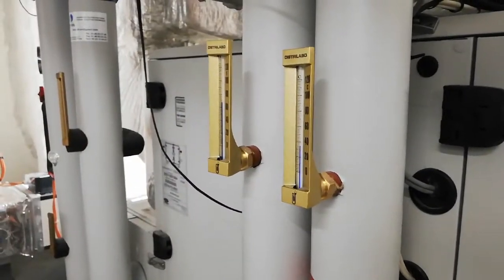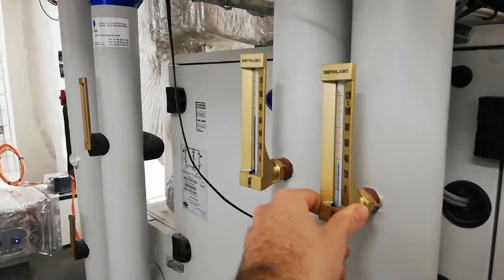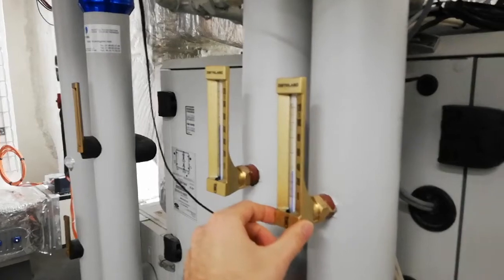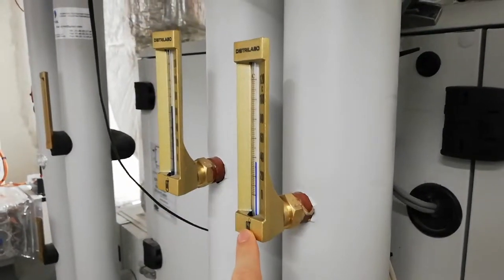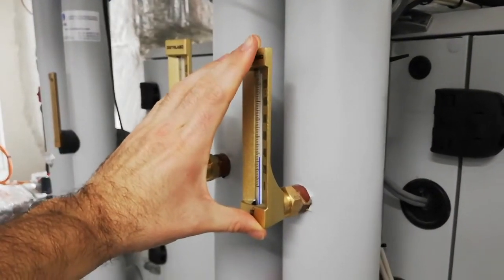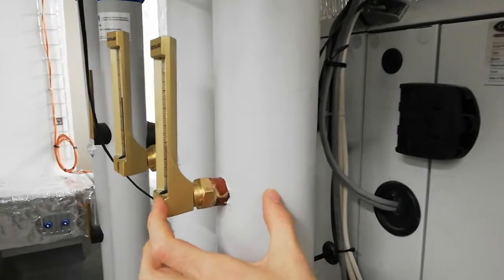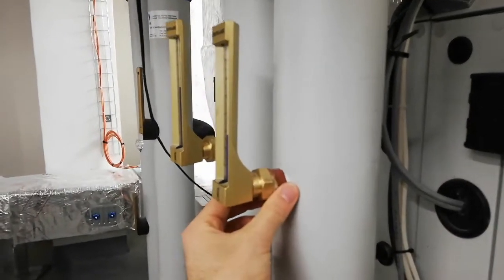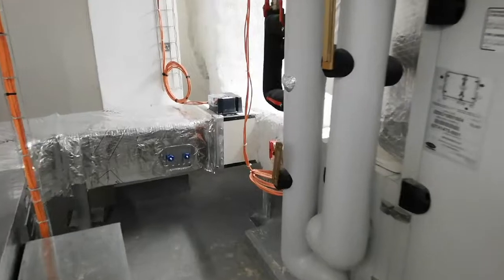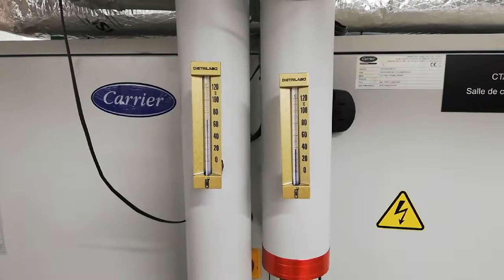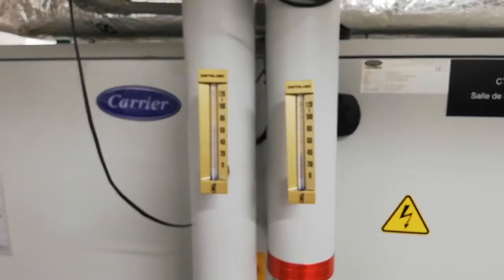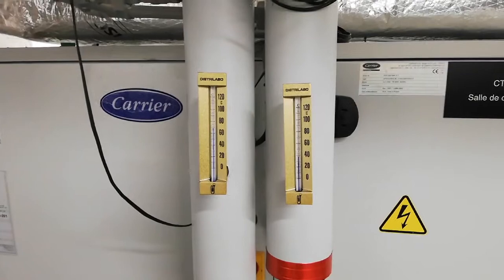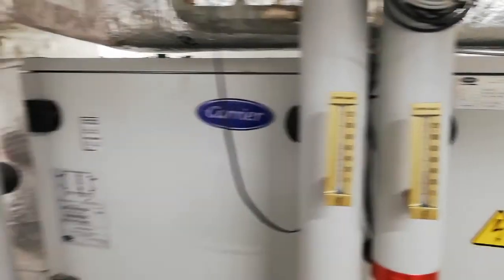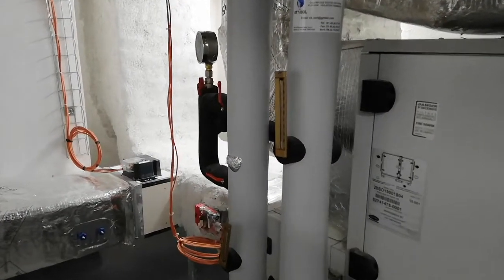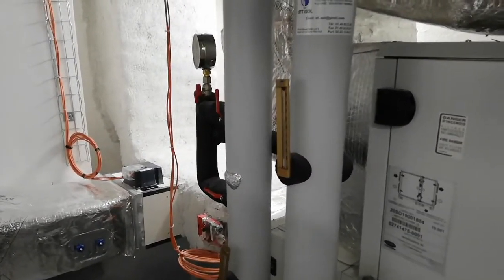Then don't forget to install industrial thermometers. These are 90 degree angle industrial thermometers, because you have this 90 degree angle here. This one has a 150 millimeter case and a 63 millimeter stem, which is the length of the small part going inside the flow to measure the temperature. We have the same on the chilled water side. The temperature range for this thermometer on the hot water coil is 0 to 120 degrees Celsius, and for the chilled water side, the range is -30 to 50 degrees Celsius.